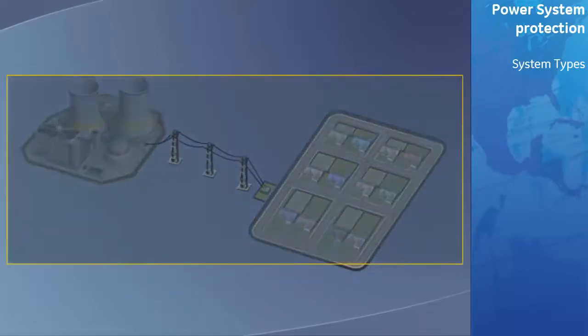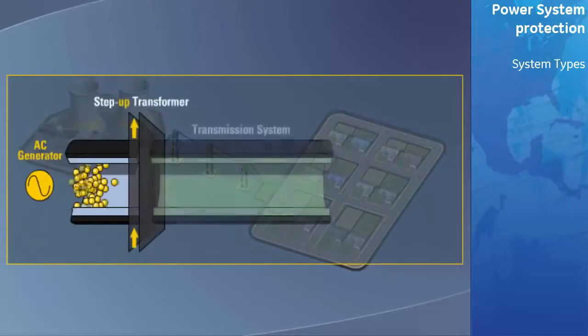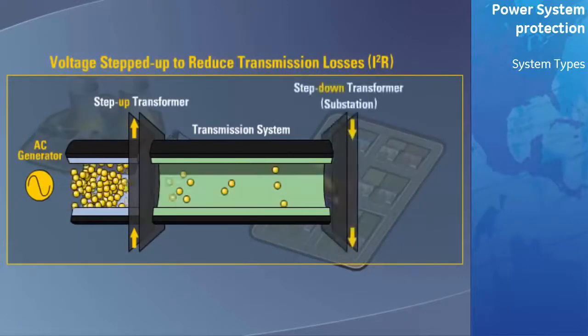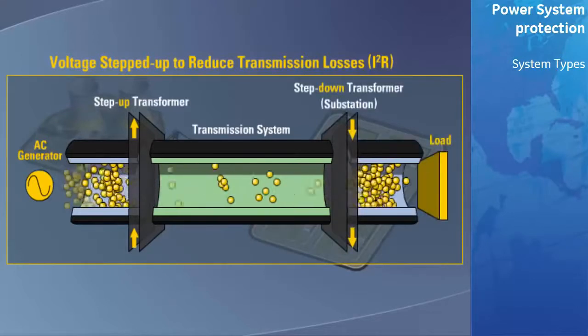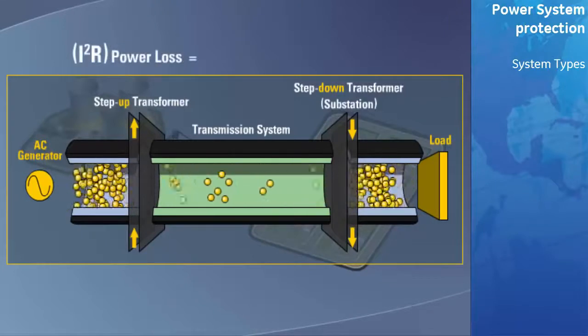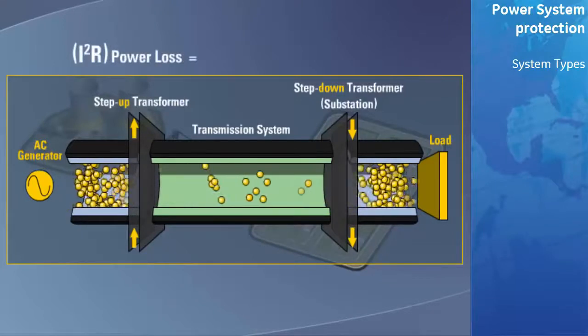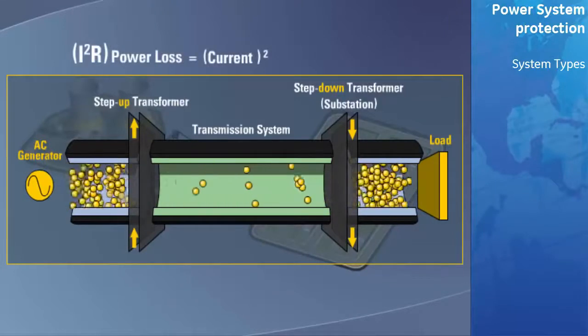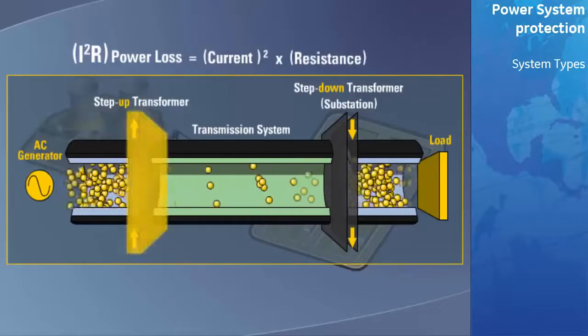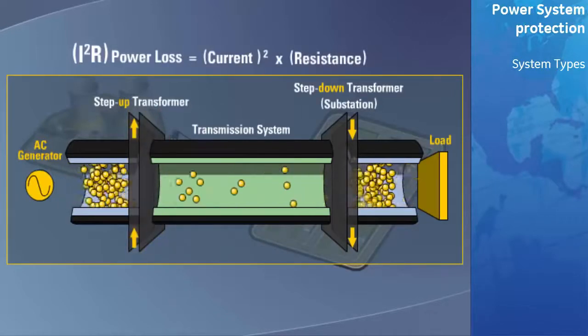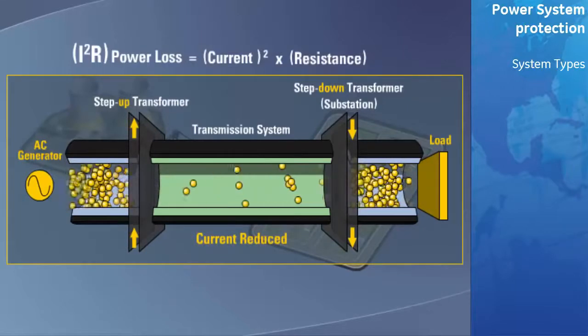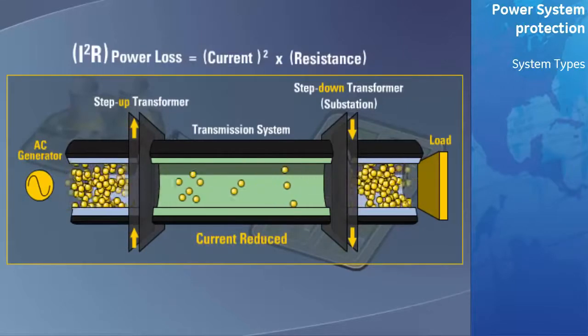Once generated, the voltage is fed to step-up transformers for transmission to reduce the I squared R losses. And then at the substation, it is stepped down for distribution. Given that the power loss during transmission is equal to the current squared flowing through the transmission line times the resistance of the transmission line, the step-up transformer increases the voltage level, thereby reducing the current, resulting in an overall reduction of power loss during transmission.